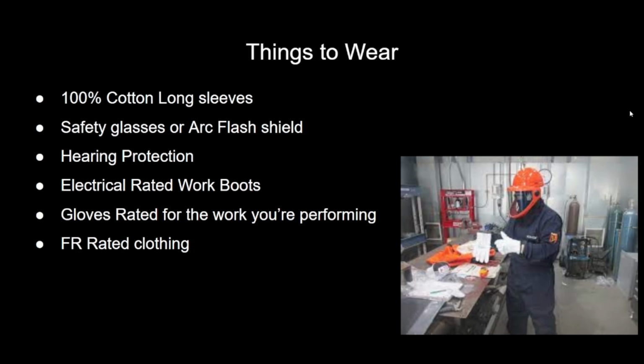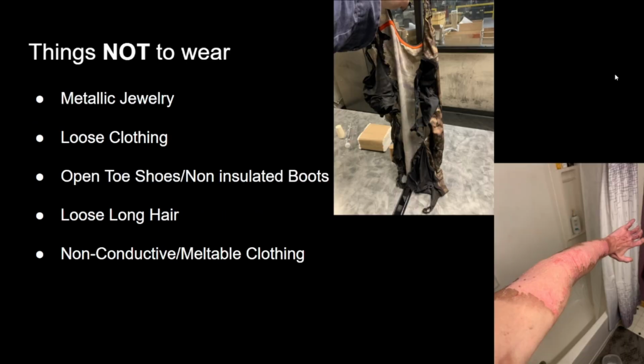Things to make sure you're wearing: 100% cotton long sleeve FR rated clothing, safety glasses or arc flash shields, hearing protection, electrical rated work boots, and then make sure you have the proper gloves rated for the work you're performing. Things not to wear: any metallic jewelry, any loose clothing, open toe shoes and non-insulated boots, loose long hair, and then this one kind of hits home for me: non-conductive meltable clothing.